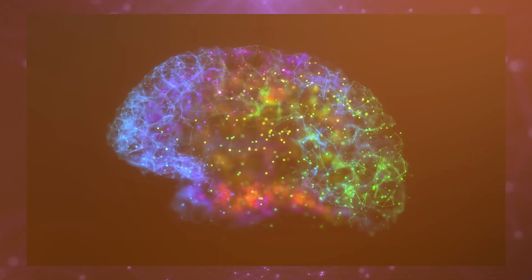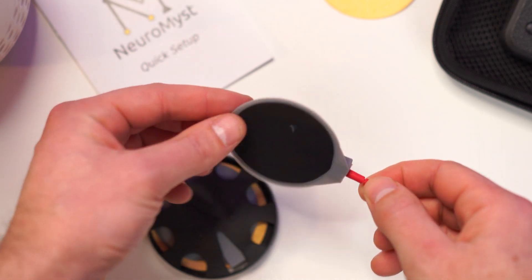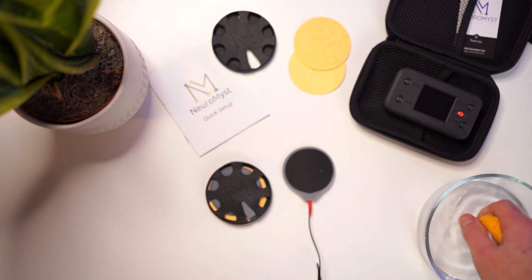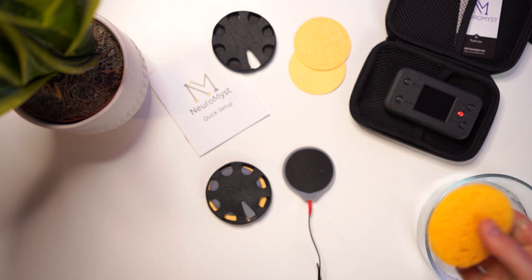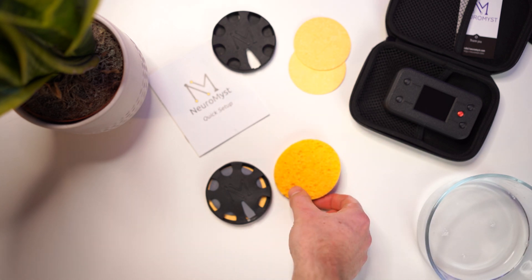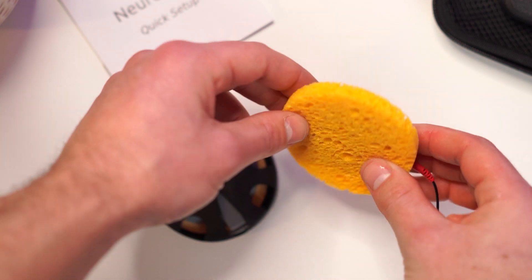Think of electrical current like water — it must always flow from one place to another. NeuroMyst safely passes current across the head using materials called electrodes. The positive electrode, or anode, is the one connected to the red wire. The black part of the electrode passes current and a sponge soaked with saline sits between the electrode and the skin. Saline has salt ions so the current can go through the sponge. The two parts together are called a sponge electrode.